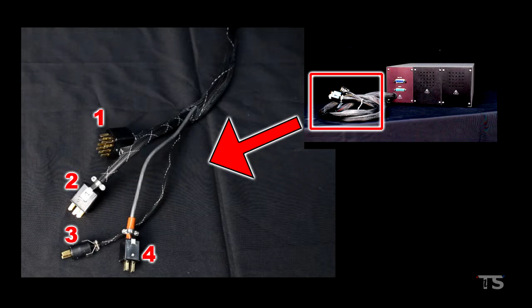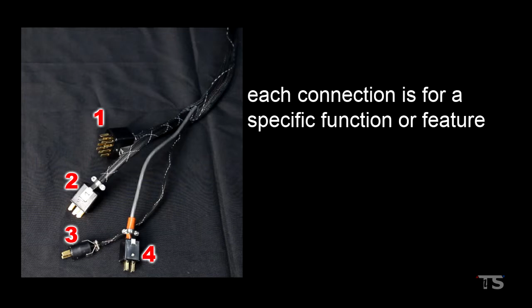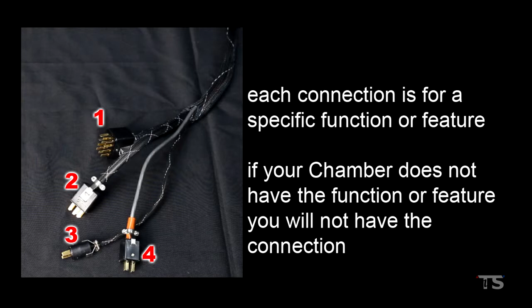This cable ends up with up to 4 separate connections on it. I say up to 4 because each of these connections is for a specific function or feature. If your thermal chamber does not have a specific function or feature, your remote controller will not have the connection for it, so don't worry if you don't see 4 connections. In this video, I will discuss all of them, but they may not all apply to you. Let's take a closer look at these 4 connections.